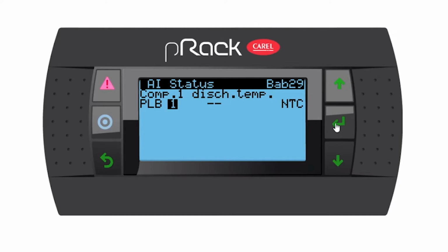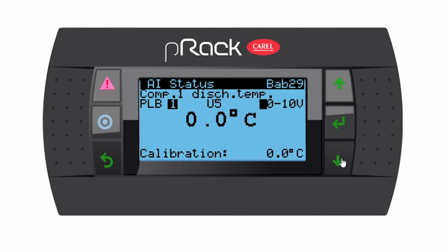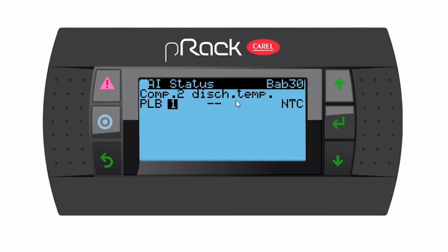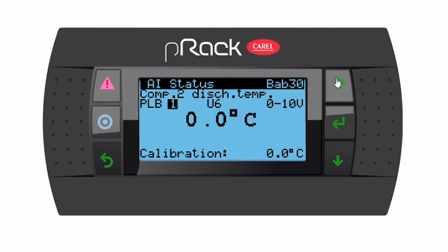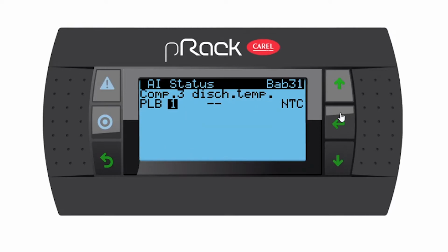Comp 1 discharge temperature. Yes, we do. So let's assign it. And it's going to be HTNTC. So here are your options. You have an option for PT1000, a 0 to 10 volt, 4 to 20 milliamp, 0 to 5 volt, HTNTC. Perfect. And there's 0 calibration. If we go down, compressor 2 discharge. I'm going to assign it to U6 and go and look for my HTNTC. Perfect. 0 calibration. Let's go down to compressor number 3. I'm going to assign it to U7. Go and look for my HTNTC again. Perfect. Enter and go down.